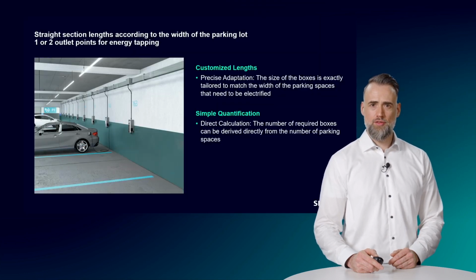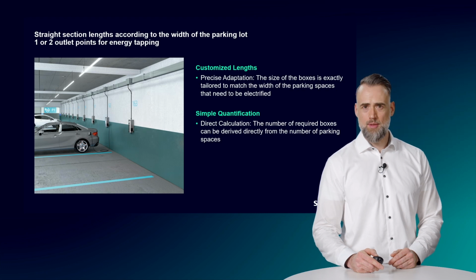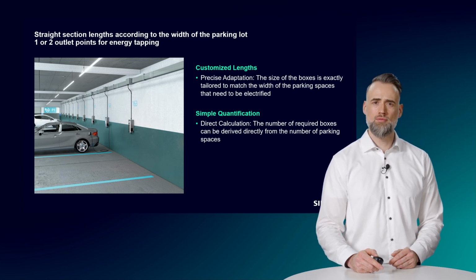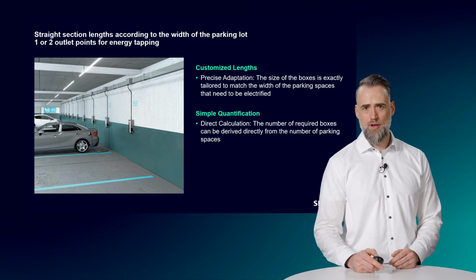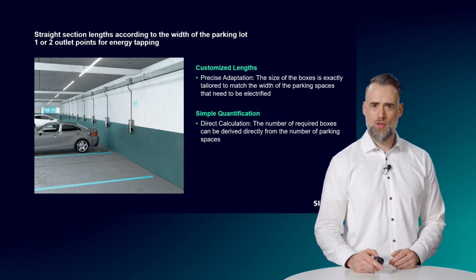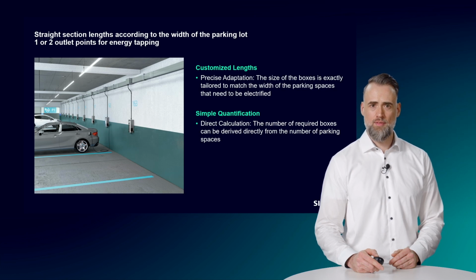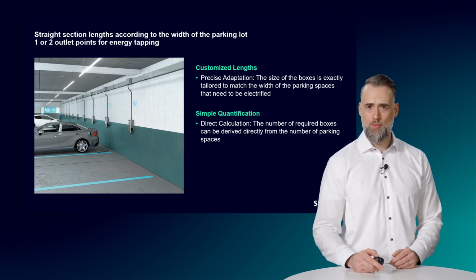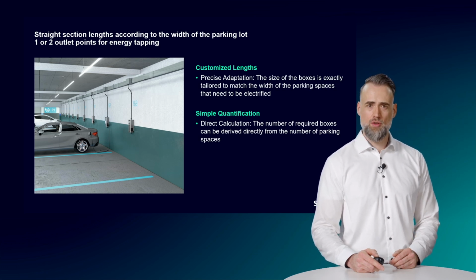The length of the busbar straight section is adapted to the width of the parking lot. All you have to know is the number of parking spaces to be electrified and you already have the required number of straight sections. And to ensure that energy can only be tapped for the wall box, these lengths are equipped with only one or optionally two tap-off points. No one can connect other consumers without authorization.